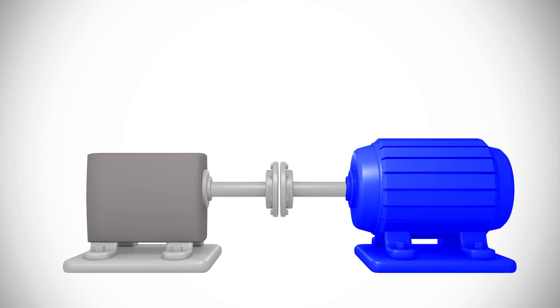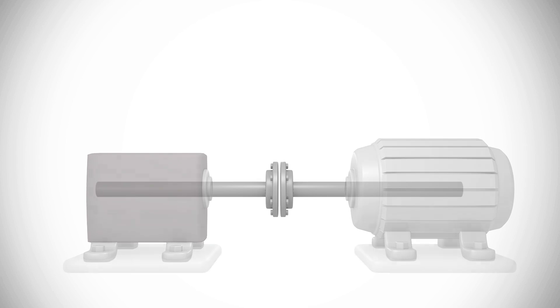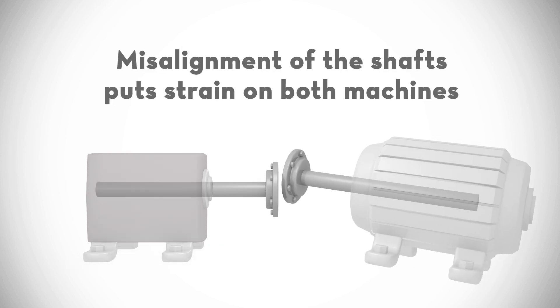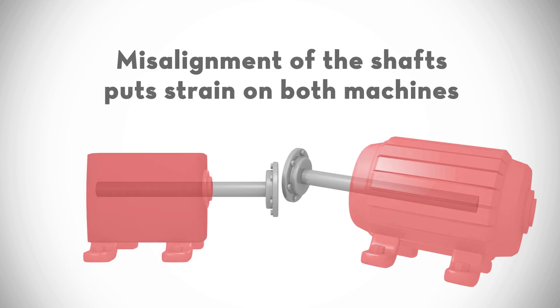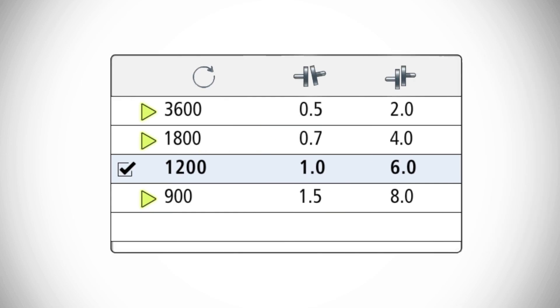The shaft in the motor or engine rotates and drives the shaft in the pump or other driven machine. Misalignment of the shafts puts strain on both the motor and the pump. It can damage the bearings, the couplings, and other machine components. For this reason, manufacturers of rotating equipment have established tolerances defining the maximum acceptable levels of angular and offset misalignment for their machines.